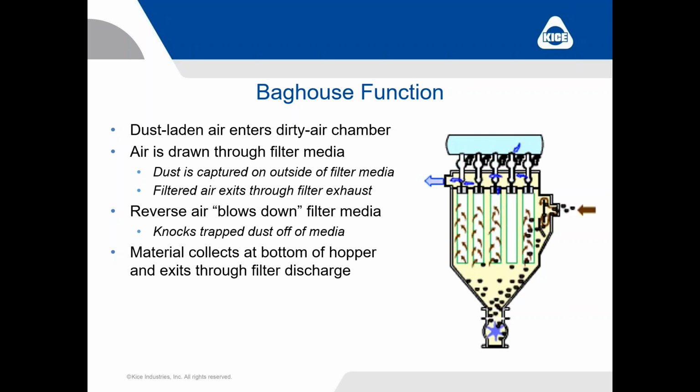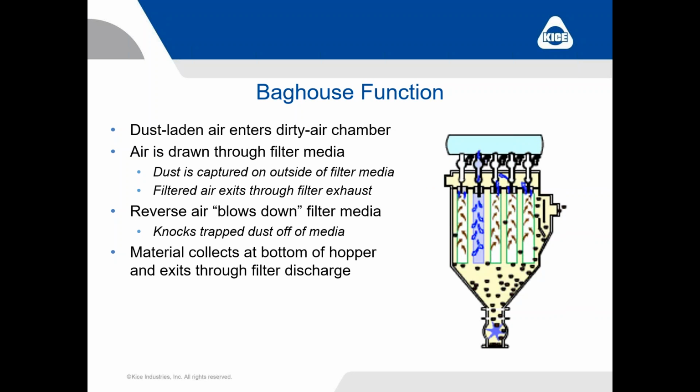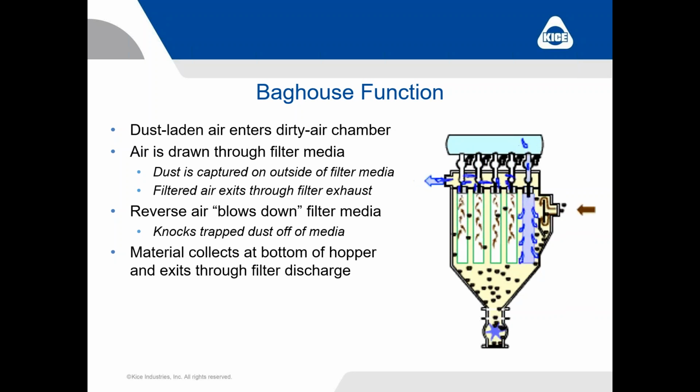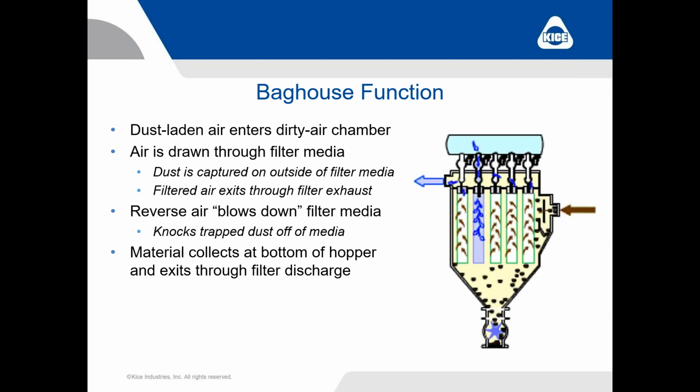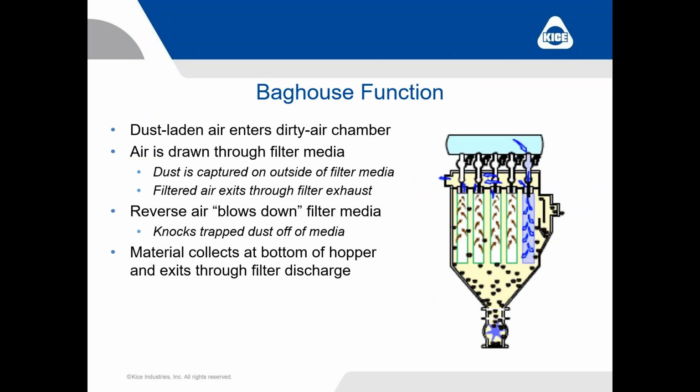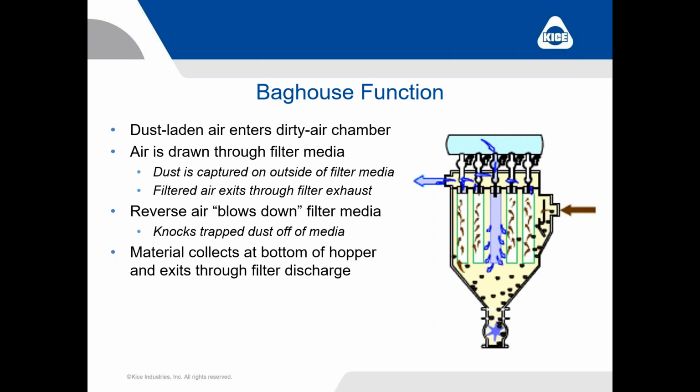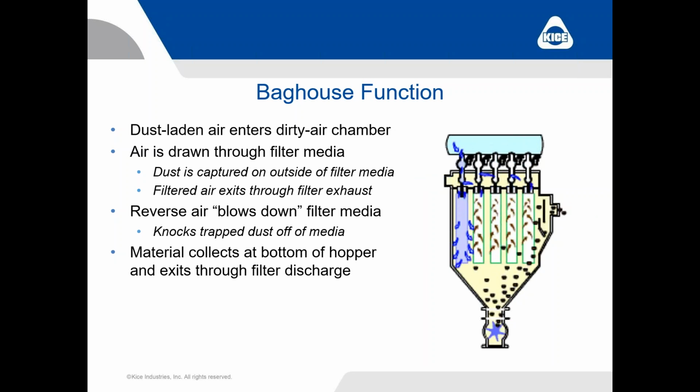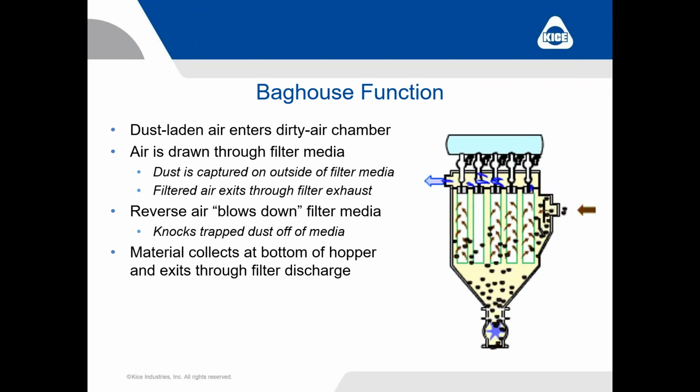So on a Kice filter, you will see a timing sequence located in the timer board enclosure, and the numbers are never in order, and that's on purpose. So if you ever notice that your blast valves are not firing necessarily in order, left to right or right to left, that's the reason why. That's just a point that I like to point out.